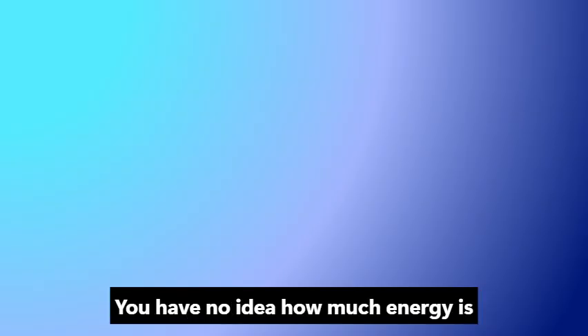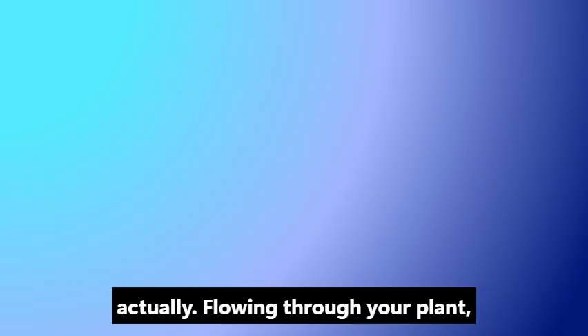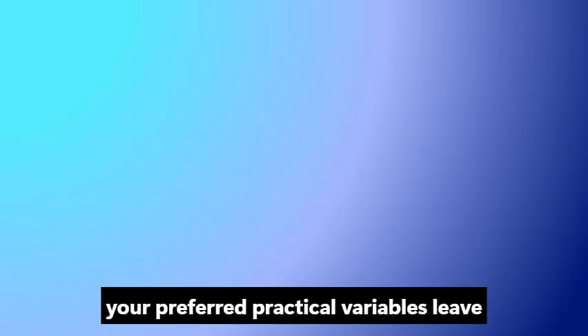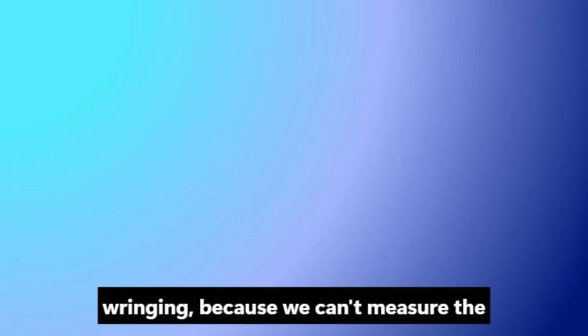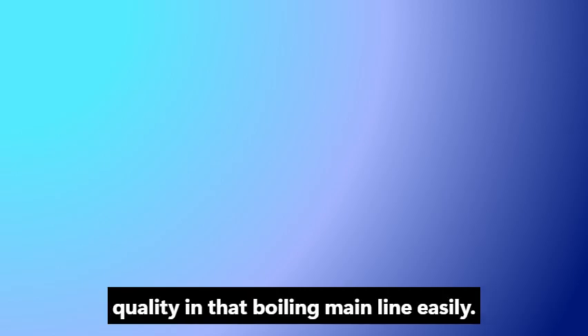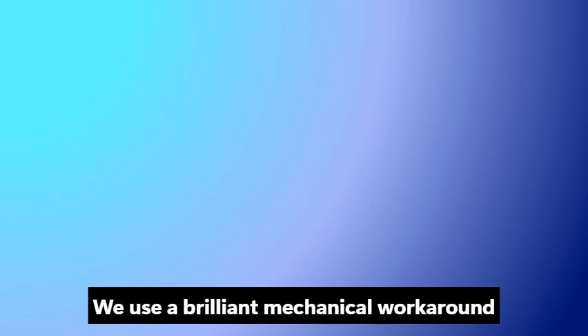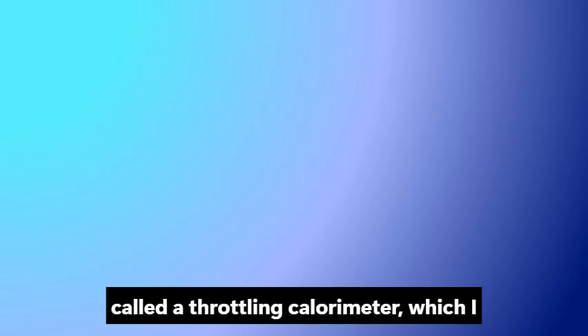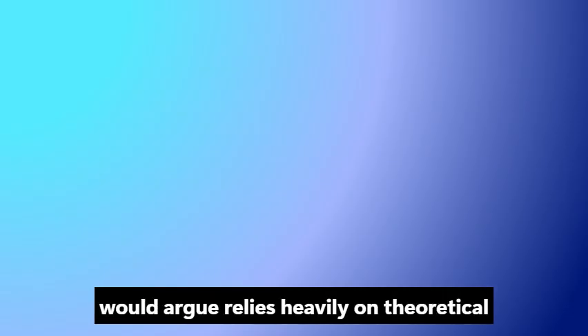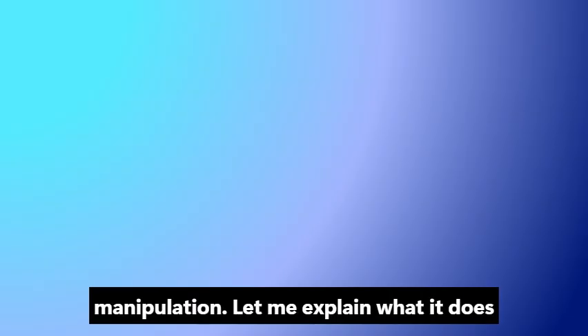Right. If you don't know the quality, you don't know the enthalpy. You have no idea how much energy is actually flowing through your plant. Your preferred practical variables leave you completely in the dark at the most critical point of the process. Well, they leave you in the dark only if you stop engineering. This is where practical application outshines theoretical hand-wringing. Because we can't measure the quality in that boiling mainline easily, we use a brilliant mechanical workaround called a throttling calorimeter. Which I would argue relies heavily on theoretical manipulation.